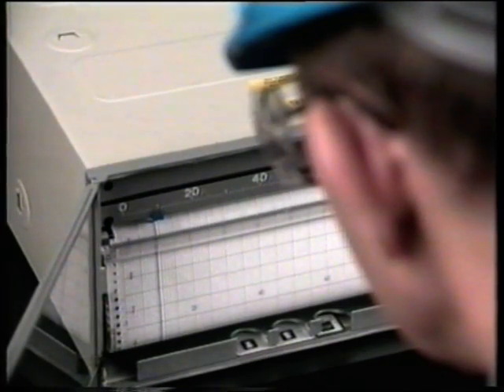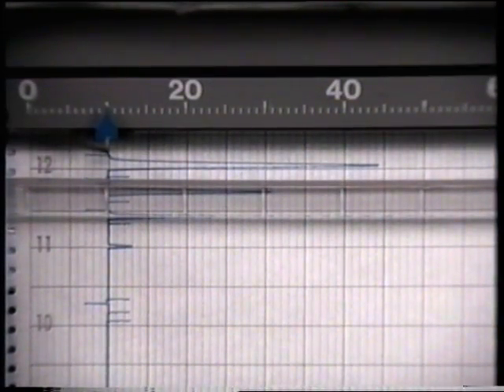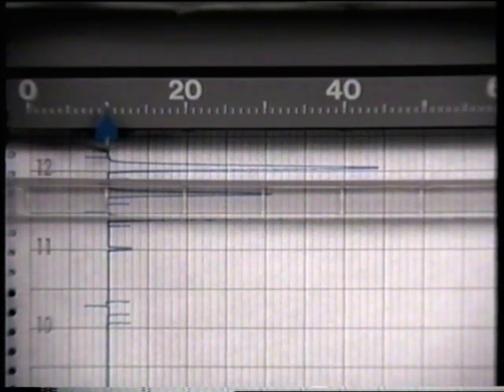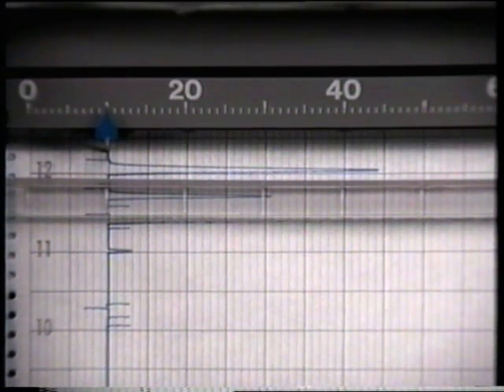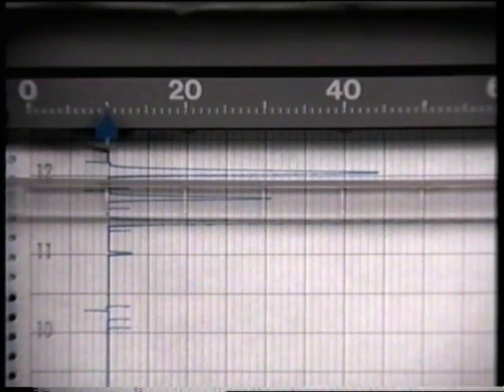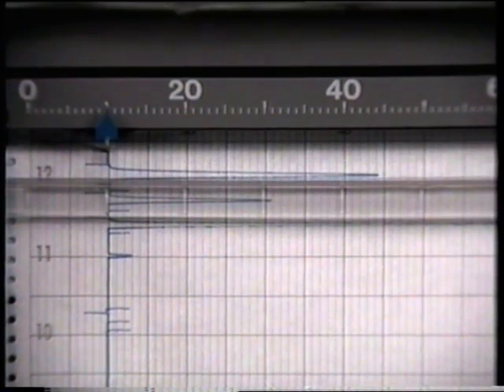Observe the baseline of the chromatogram for a few minutes. If it's drifting excessively, the detector is probably not quite up to temperature. Wait until the baseline is stable. If some peaks are off scale, adjust the range up. If all of the peaks are too small, adjust the range down.